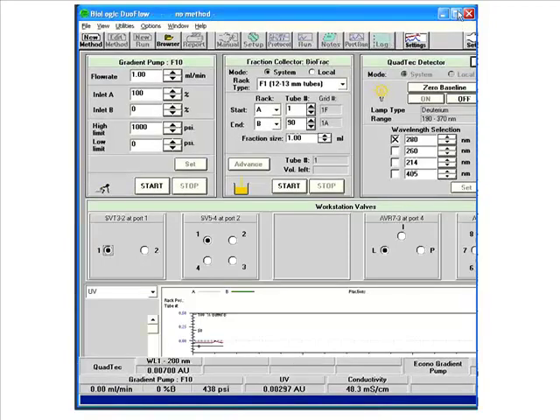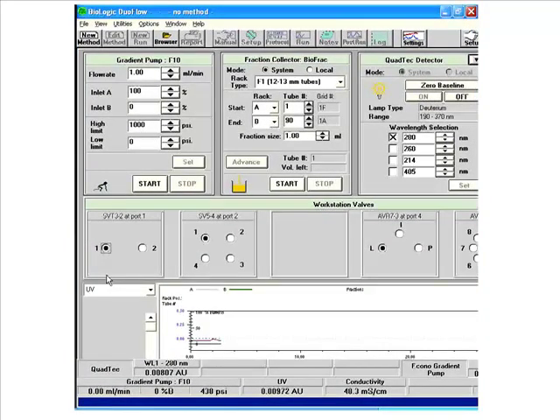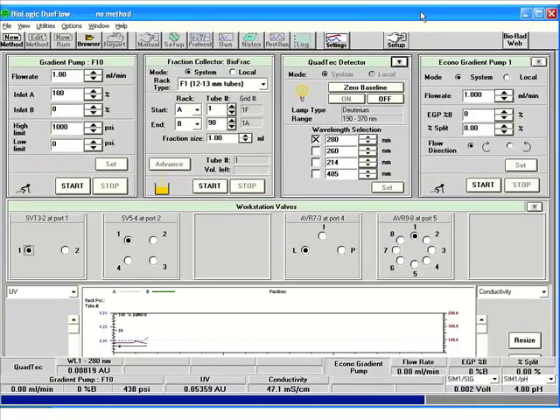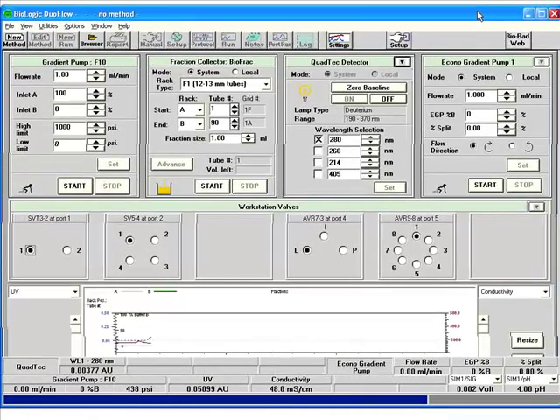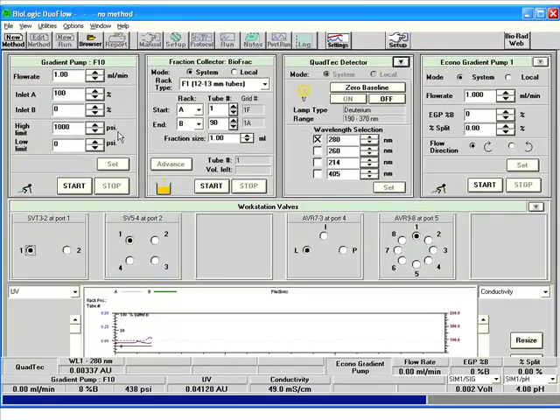This is Sean Taylor from Biorad Canada. I'm a field application specialist with the company and today I'm going to be talking to you about the DuoFlow software package. DuoFlow software is the package that runs our chromatography systems, our high-end pump-based systems with two sapphire piston heads for pump A and B to give you very precise flow rate control all the way up to 3,500 psi if you're working with our basic system. So when you open the software, you open into our manual screen.